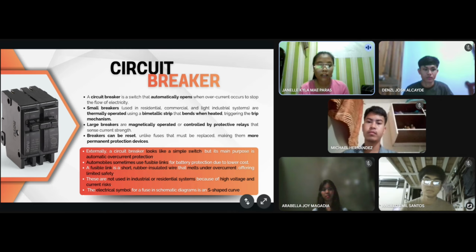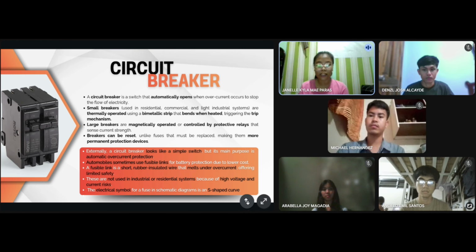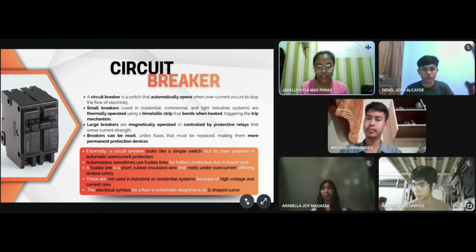Next is circuit breaker. A circuit breaker is a switch that automatically opens when overcurrent occurs, stopping the flow of electricity to protect the circuit. Small breakers, which are commonly used in residential, commercial, and light industrial systems, are thermally operated using a bimetallic strip that bends when heated, triggering the trip mechanism. Large breakers, on the other hand, are magnetically operated or controlled by protective relays that sense the overcurrent strength.